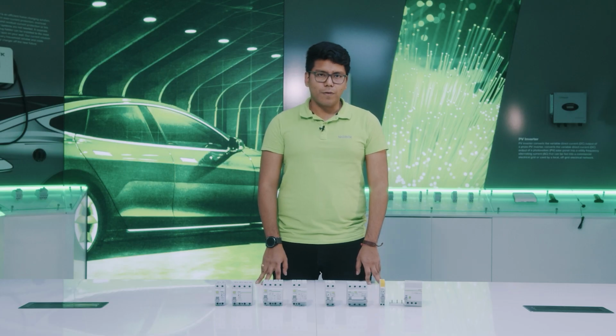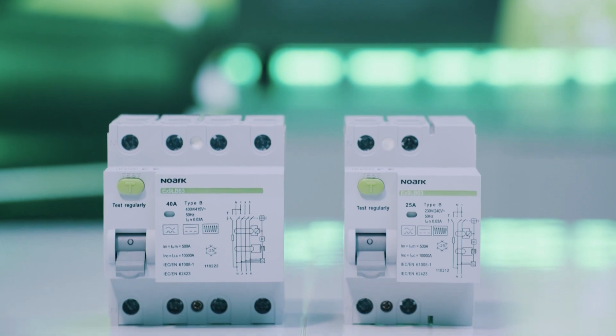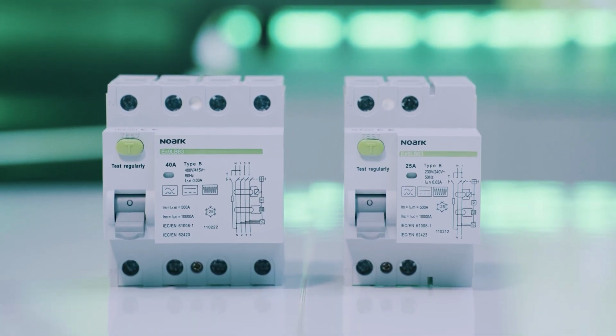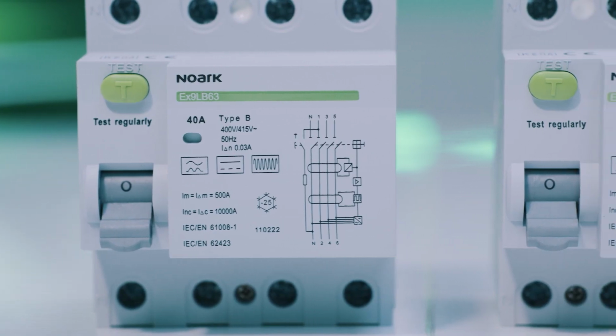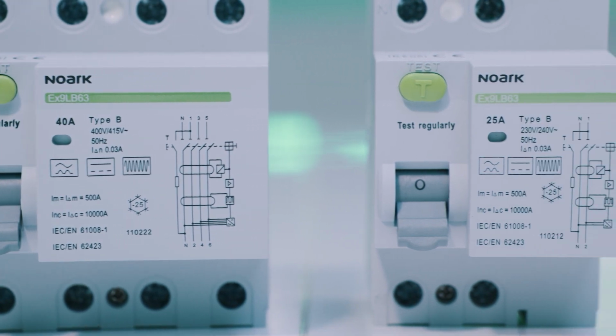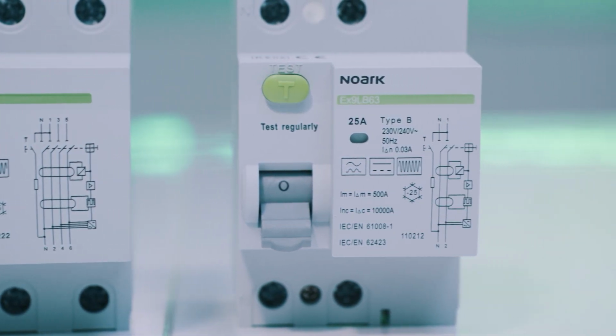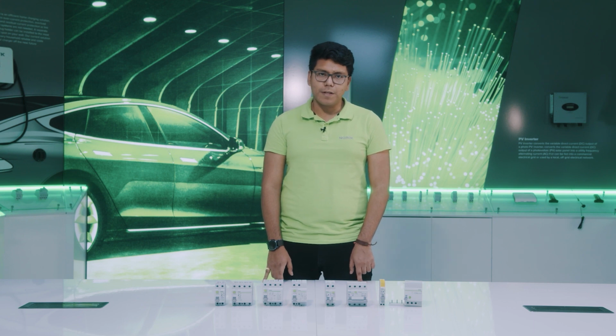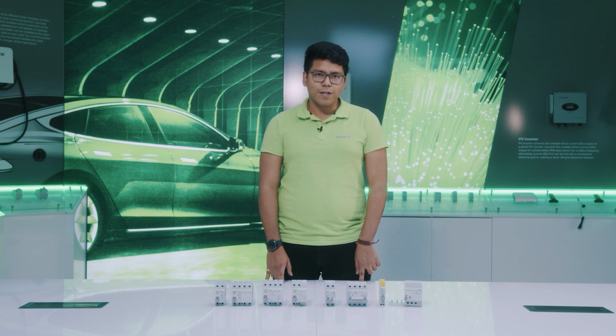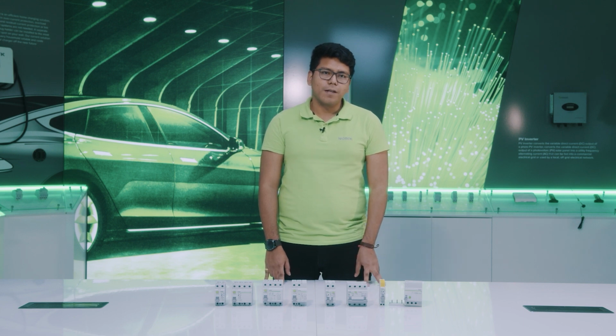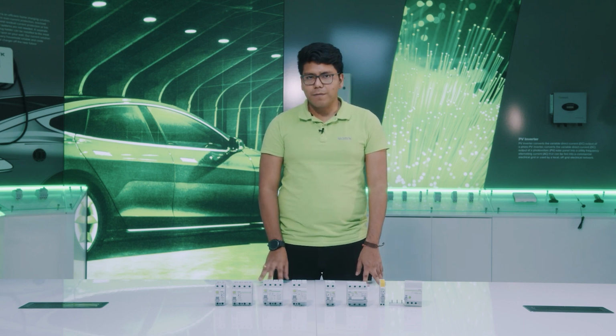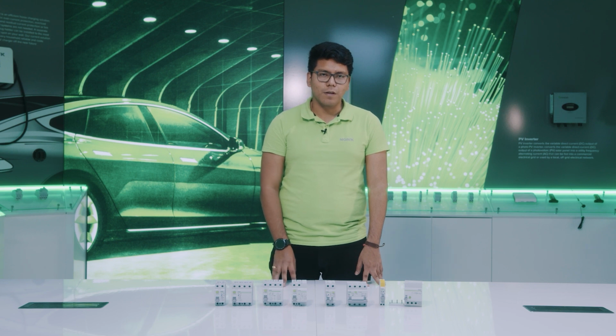Type B is suitable for AC, pulsating and smooth DC currents up to 1 kHz. This type can be used for almost every application solution, from photovoltaics, EV chargers, elevators, motor drives, and so on. Another important parameter is the sensitivity of residual current over which the RCD device will trip. It is separated into high sensitivity, mainly for life protection, and medium sensitivity for building and machinery protection.